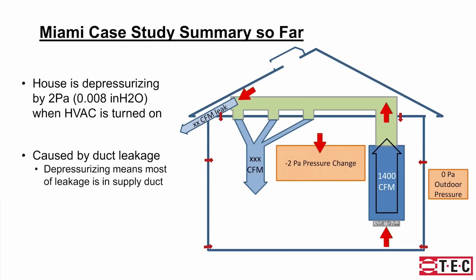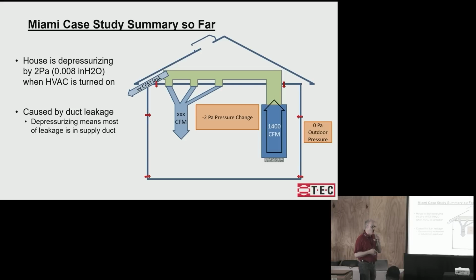Okay? And we know that because some of the air is not coming back in, the amount of air coming back into the house is less than 1,400, because some of it's leaking out and falling out the soffit vents or whatever. And so what that means is that the house is minus 2, and it has to make up the difference between how much is coming in and how much is going out. And that difference will always get made up by sucking air through all the cracks in the house. Okay, how do we know there's air coming in? Could it be the case that the air is not coming in? Exactly. That's exactly right. We know the difference is being made up because the house did not collapse. Okay?